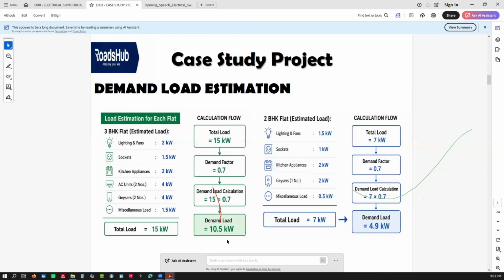I have a demand load of 10.5. That's greater than 7. For this other one, I'll do a single-phase system. In this case, I'm talking about DBs because that's the next slide. So you have a demand of 4.9. That's even less than 5. You cannot build a 3-phase DB there because we have different types of DBs. We have 3-phase DBs and we have single-phase DBs, which are called consumer units. Single-phase DBs, consumer units. 3-phase DBs, the DBs you know now.